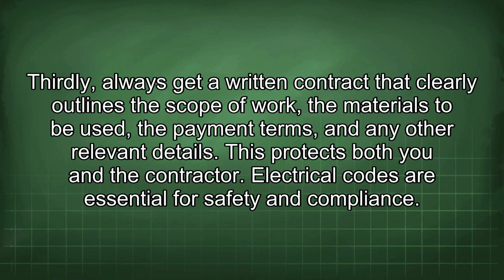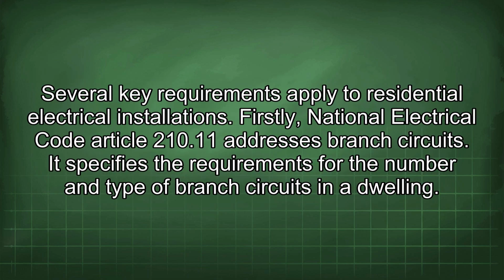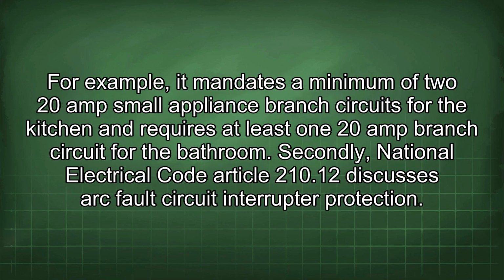Electrical codes are essential for safety and compliance. Several key requirements apply to residential electrical installations. Firstly, National Electrical Code Article 210.11 addresses branch circuits. It specifies the requirements for the number and type of branch circuits in a dwelling. For example, it mandates a minimum of 2 20-amp small appliance branch circuits for the kitchen and requires at least one 20-amp branch circuit for the bathroom.